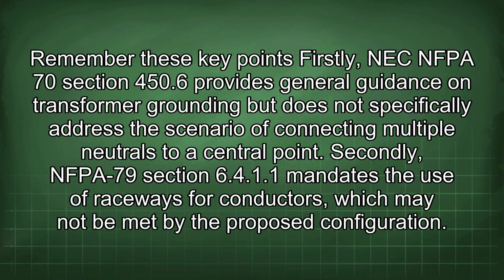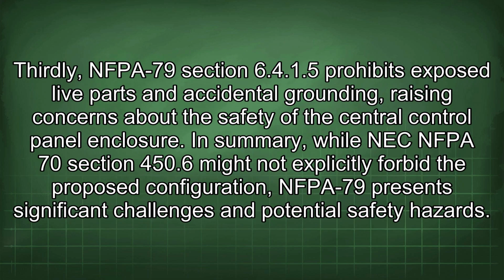Remember these key points. Firstly, NEC NFPA 70 Section 450.6 provides general guidance on transformer grounding but does not specifically address the scenario of connecting multiple neutrals to a central point. Secondly, NFPA 79 Section 6.4.1.1 mandates the use of raceways for conductors, which may not be met by the proposed configuration. Thirdly, NFPA 79 Section 6.4.1.5 prohibits exposed live parts and accidental grounding, raising concerns about the safety of the central control panel enclosure.